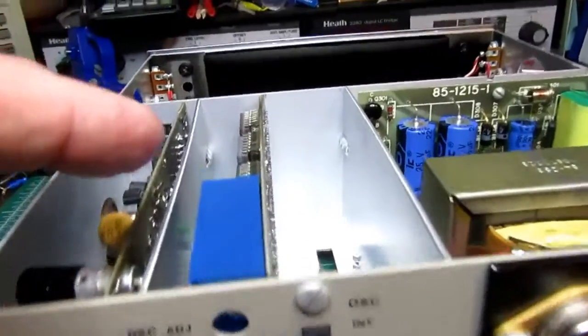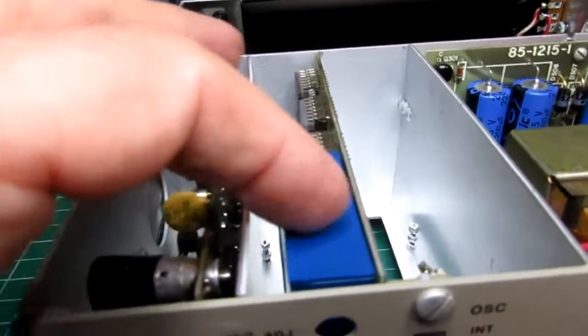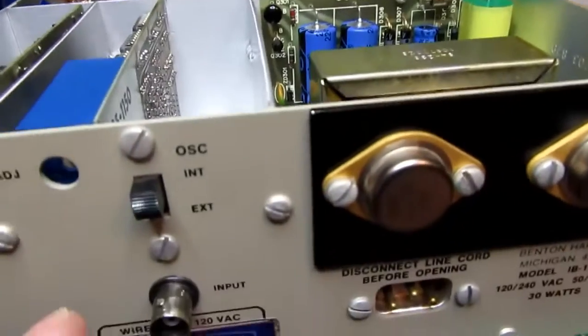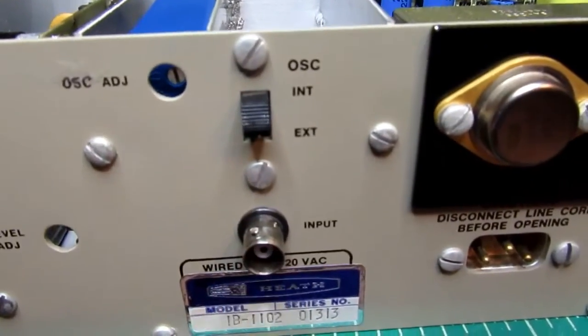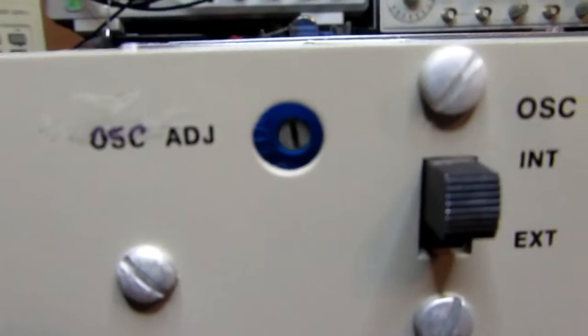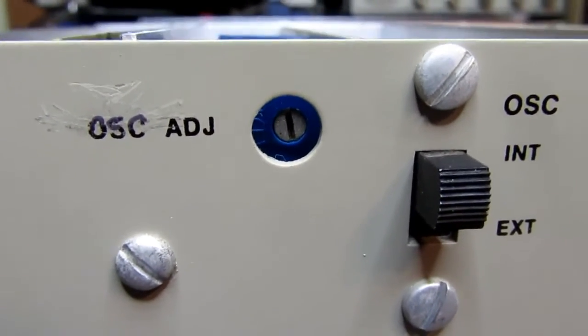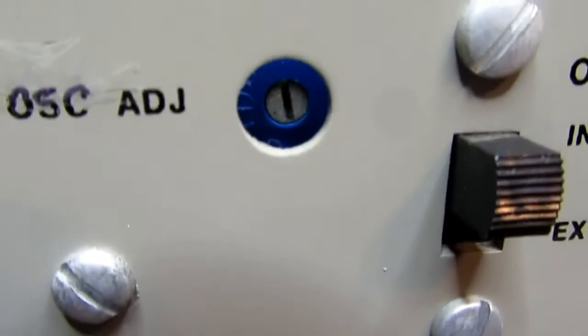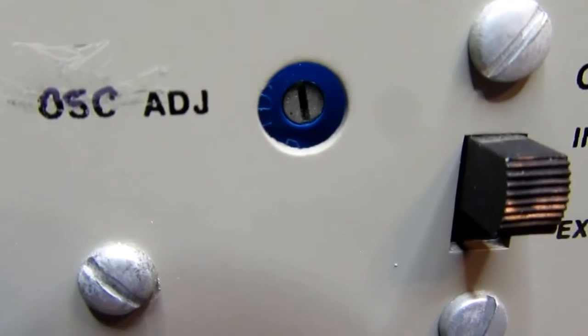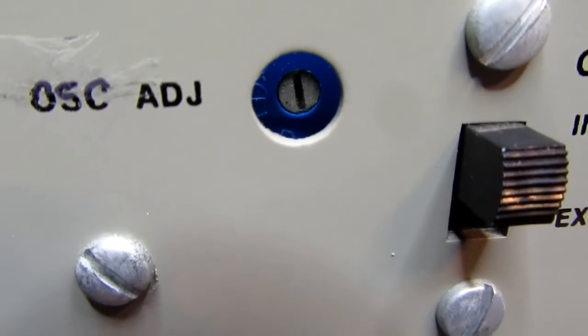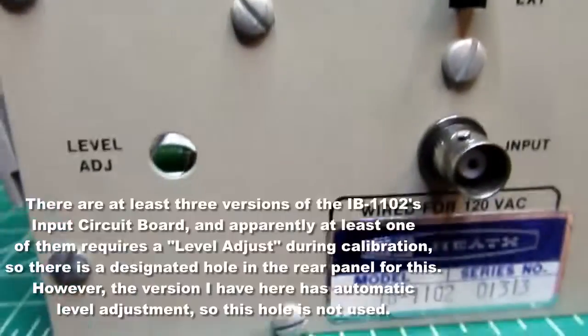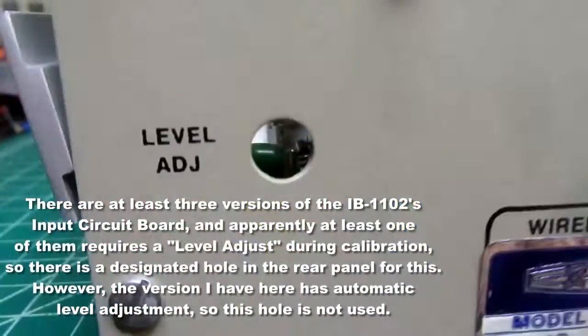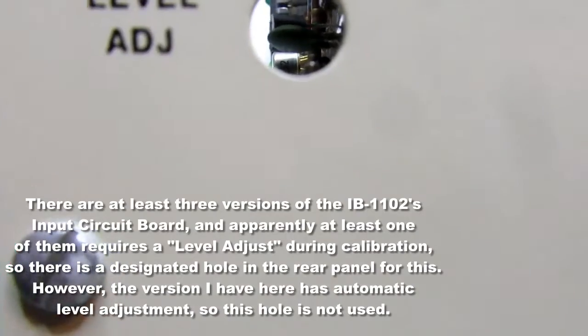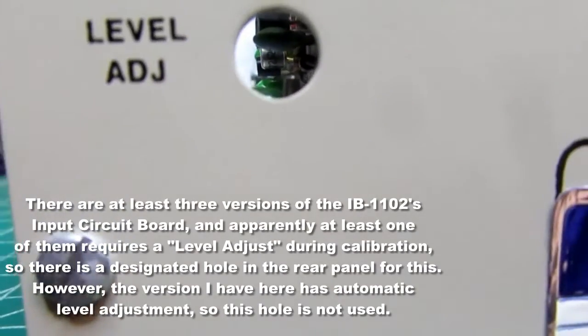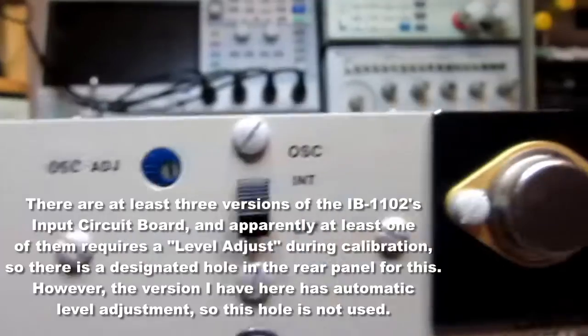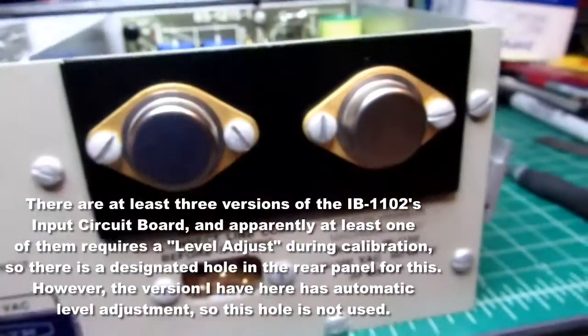The part that's the clock, really the part in the blue housing here, gets replaced then with the signal coming in here. There is an oscillator adjust. It's factory calibrated, but you can see there's an adjustment there, hole through the rear of the case, and then a screwdriver slot inside the blue housing. And then on the front end board there's also a level adjust, which is back in there somewhere. It's kind of hard to see what it goes to.